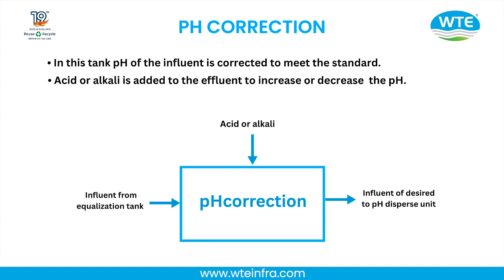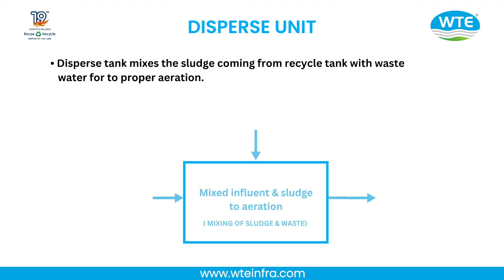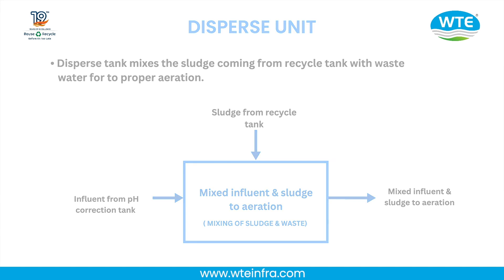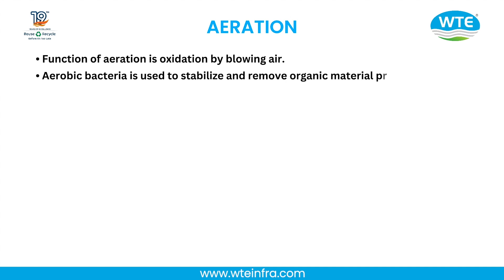pH Correction: The pH of the influent is corrected to meet the standard. Acid or alkali is added to the effluent to increase or decrease the pH. Dispersed Tank: Mixes the sludge coming from the recycled tank with the wastewater for proper aeration. Aeration: The function of aeration is oxidation by blowing air. Aerobic bacteria are used to stabilize and remove organic material present in the waste.